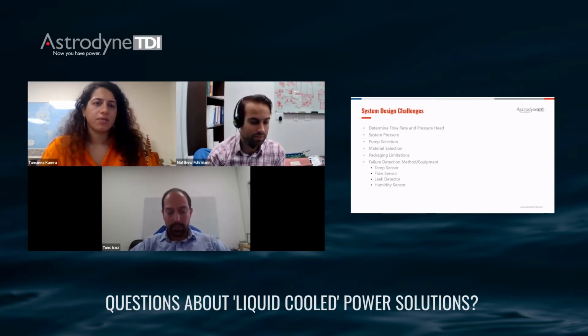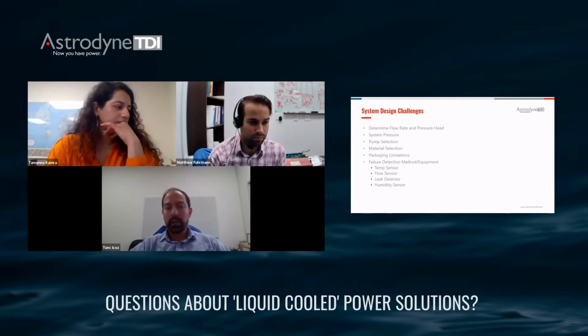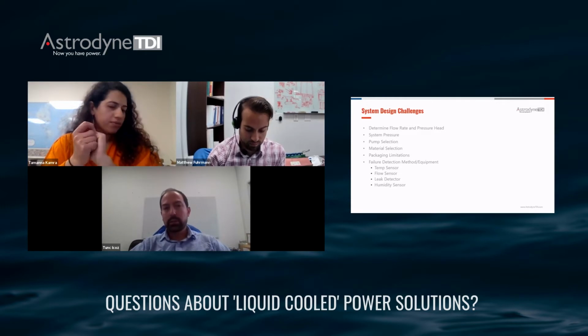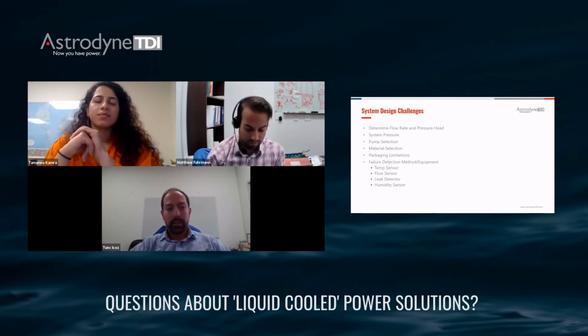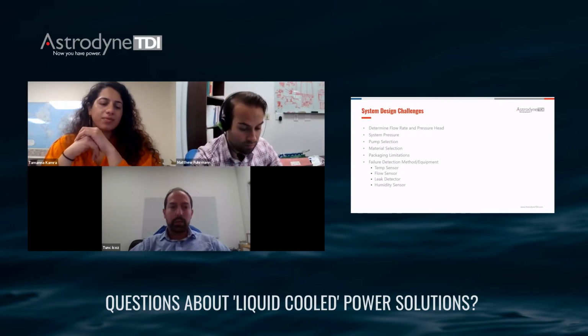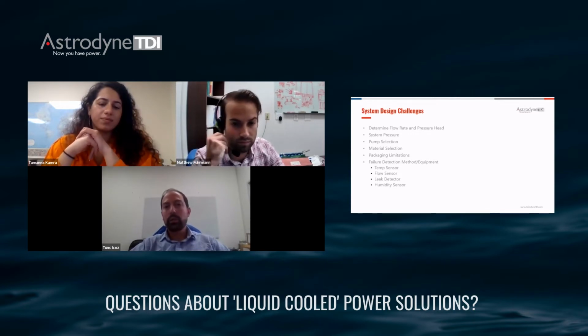I think we can't emphasize enough the design consideration on the condensation in a water-cooled system. So oftentimes, we come across applications where the cabinet needs to be sitting in an outside environment, and the coolant temperature is not controlled. And then we bring up with every customer that there's a concern if the temperature drops below the dew point in a high humidity environment. The system needs to be protected, and I think that's oftentimes overlooked, and it's a second thought. So we really want to bring that up as one of the really hidden design challenges.